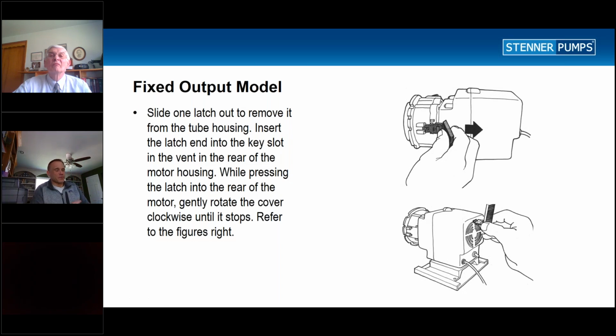Okay, so we went through the tube change on the pump itself. When we're changing the tube, I always recommend, when you're engaging the rollers going in the clockwise motion, you'll notice in the video they were holding down the head. If you don't hold the head down and you're trying to expand the rollers, it will, how can I say it, it will turn the whole head. So you want to try to keep that in place. I have a slide here.